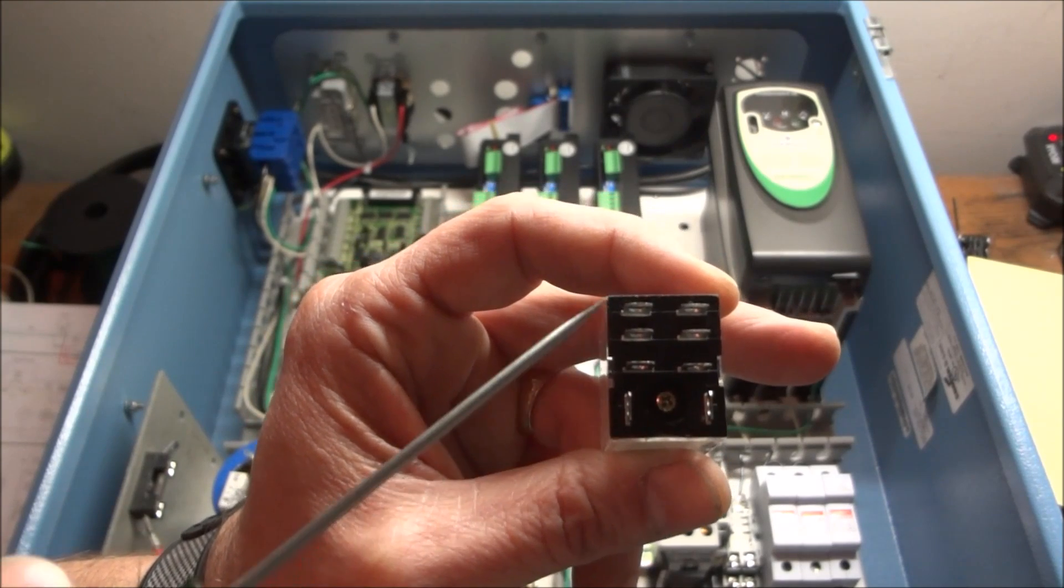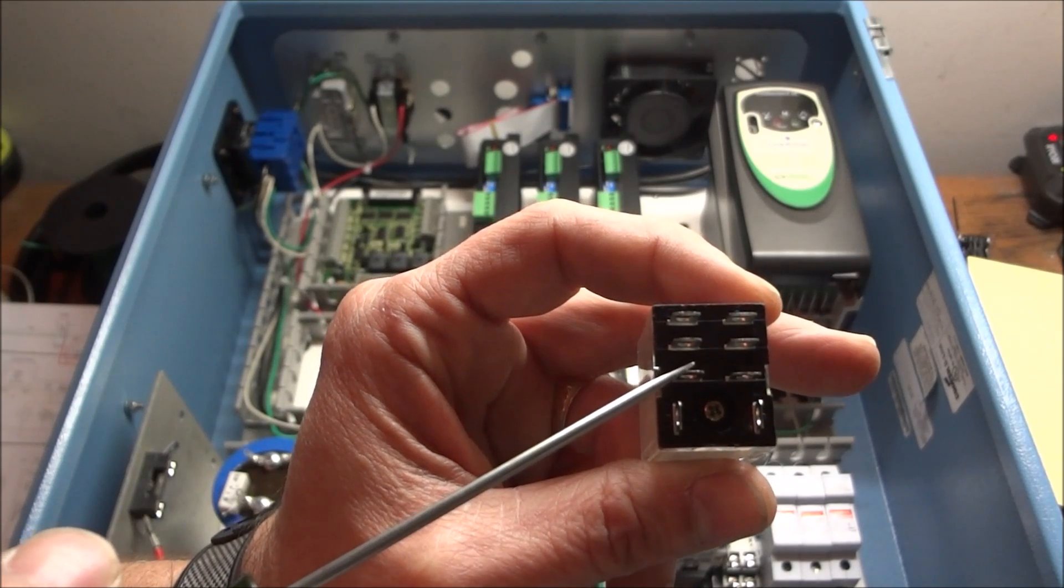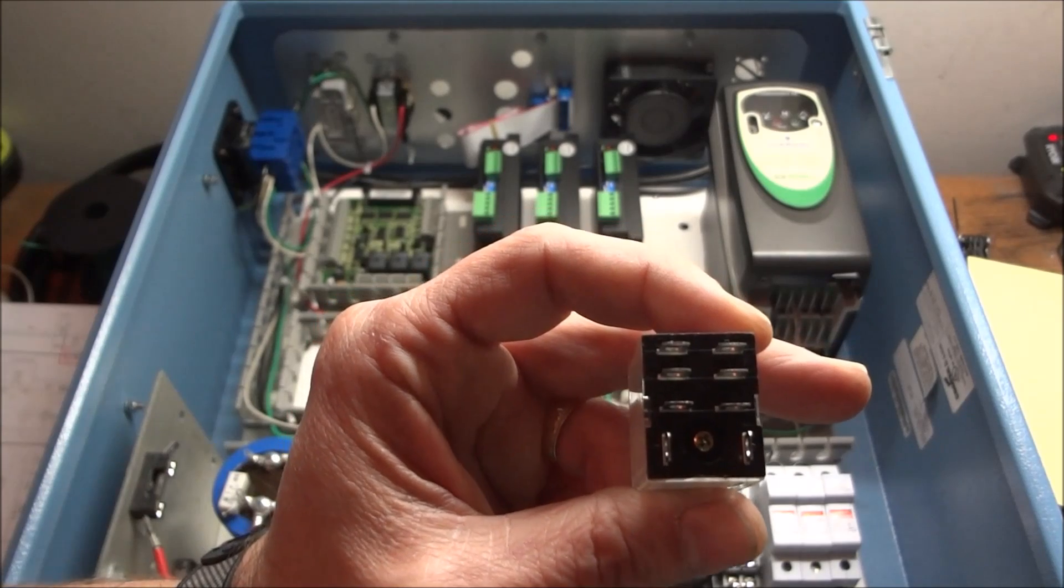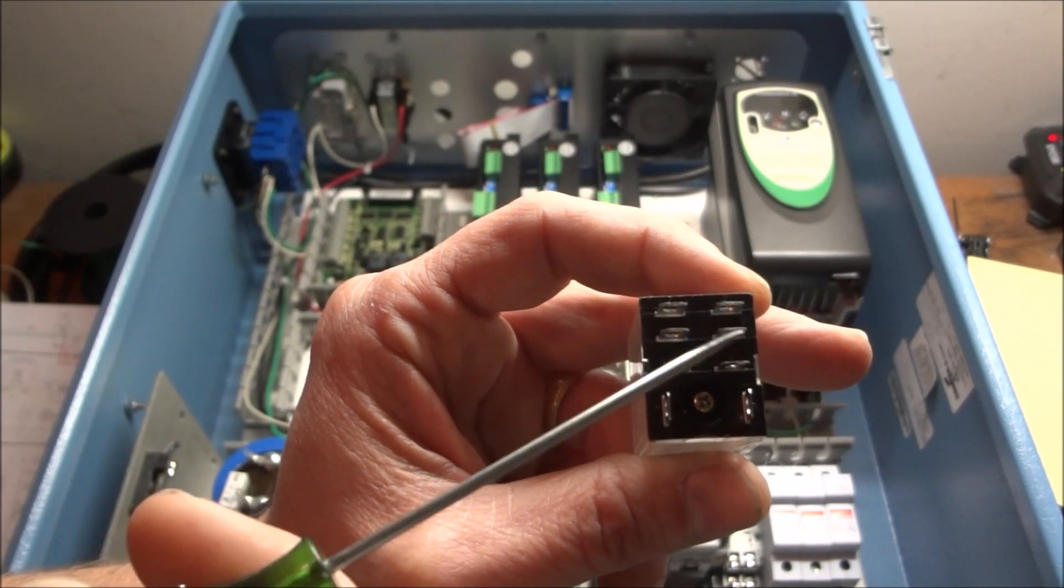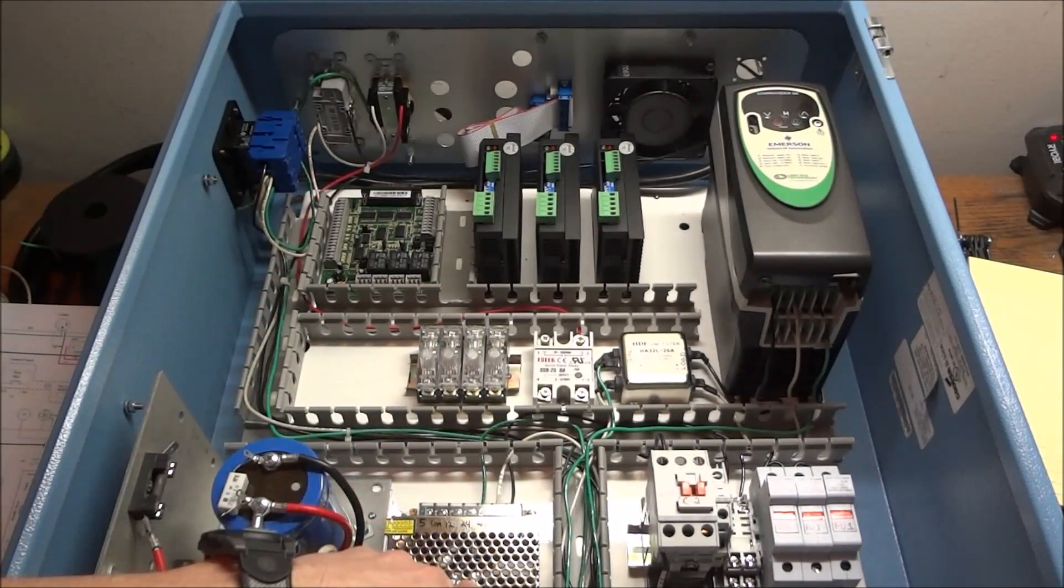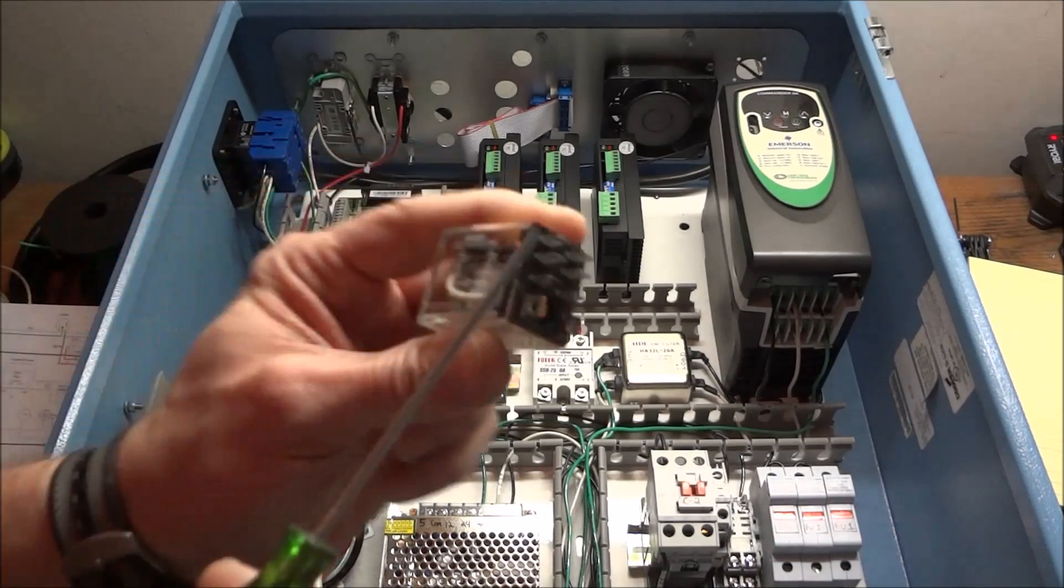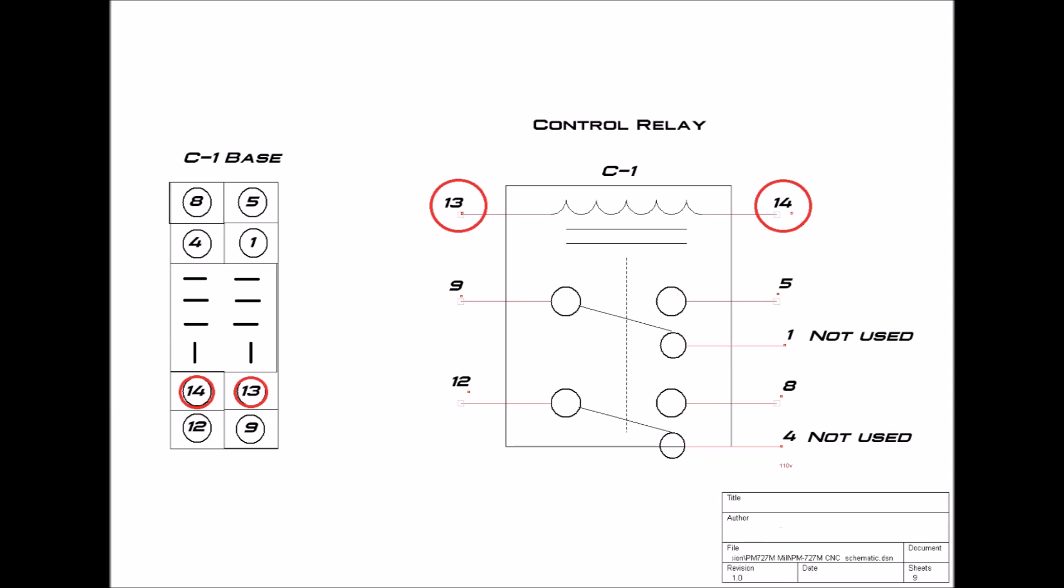Once power is applied to the coil, it switches and these are our contacts. These are our normally open contacts, and this between here and here is the switch, and here and here is the switch with power applied. So we will be using these two center contacts for our two C1 contacts to turn on our tri-power power supply and our 48 volt power supply. The normally closed contacts we will not be using at this time.